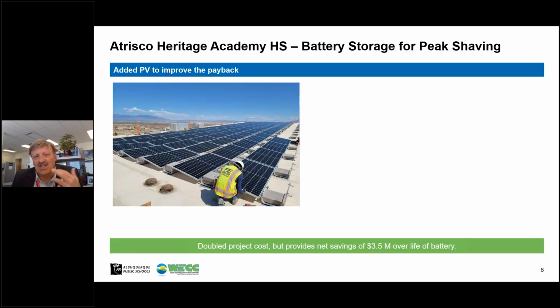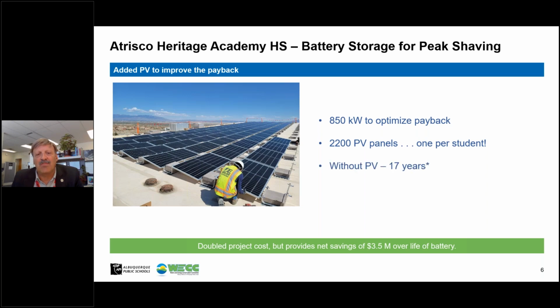So part of the consideration when we looked at the finances of it was, does it pay for itself? And our contractor helped us realize if we put solar with it, we could definitely reduce the payback. So the 850 kilowatts is about 2.5 times larger than any other solar installation we have in the district. We have almost 30 solar installations on schools. And the payback for the battery by itself was approximately 17 years, and I've got an asterisk there.